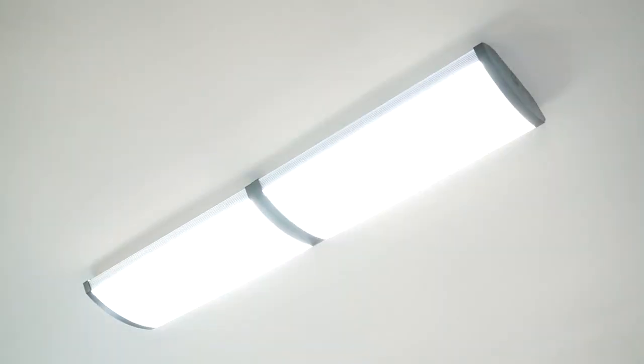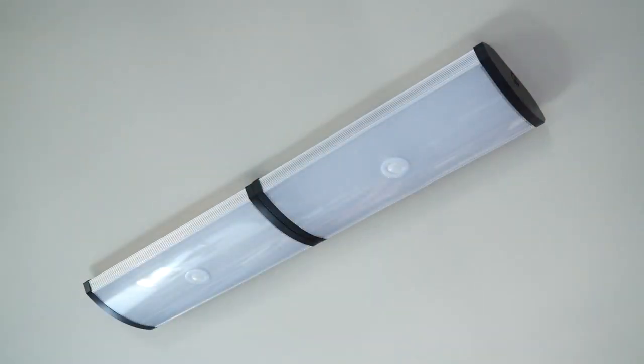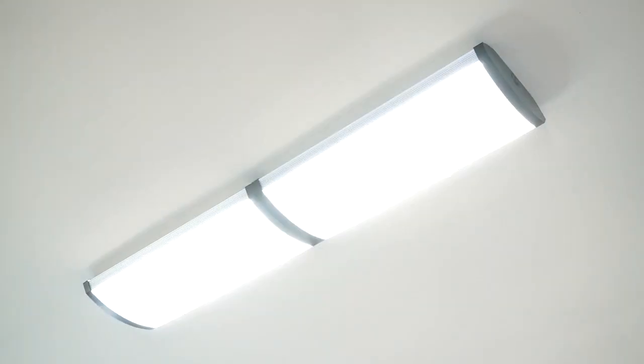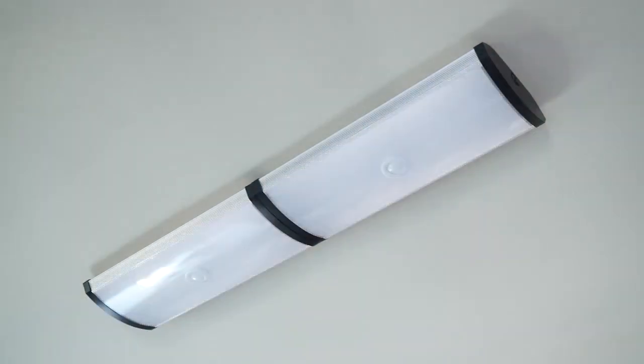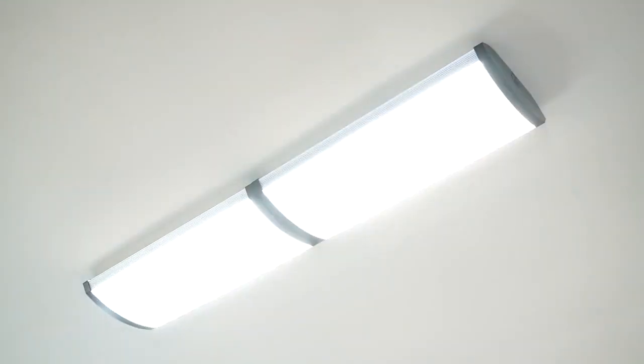Turn on the electricity at the circuit breaker box and walk back into the room where the fixtures are installed. The lights will turn on automatically as soon as motion is detected in the room by the PIR sensors. Verify the PIR sensors are working properly by exiting the room and wait to see if the lights turn off in the selected time frame.